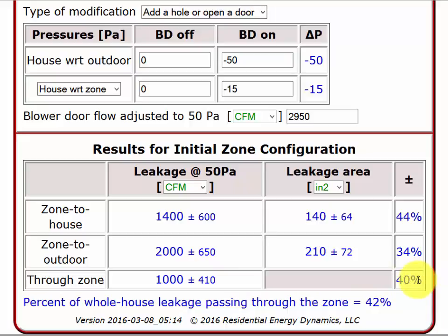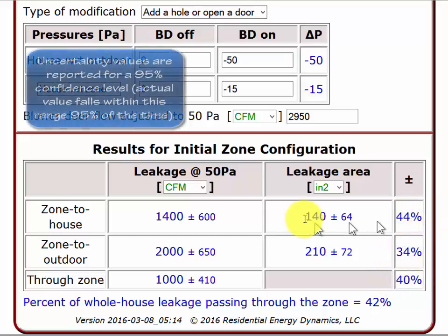So these are very powerful results. We can do a lot with these. Just a few words about uncertainty over here, and the uncertainty absolute numbers listed after these values. Zone pressure diagnostics has always had uncertainty attached to it, but what we chose to do here is show you what it is. And I wouldn't worry about this uncertainty. There are things you can do to lower these numbers, these percentage numbers and the values here. The ones here are not really out of line. They're in a pretty good range. There can be uncertainty percentages and values that are much larger than these.